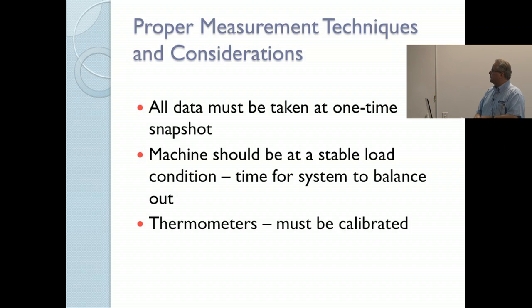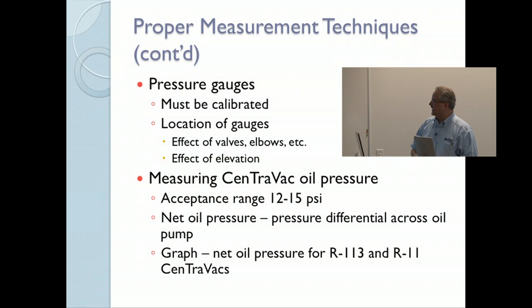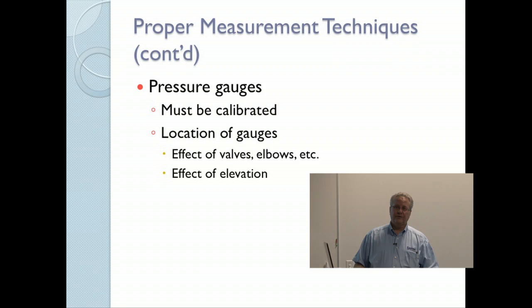Some proper measurement techniques and considerations. Again, all data needs to be taken at one time. It's like a one-time snapshot. You don't want to take half the data and then come back an hour later and take the rest. You need to take it all at one time so you can see a snapshot of where you're at. Also, the machine should be at a stable load condition. You want the time for the system to balance. You don't want it while it's hunting. Particularly if you're first turning the chiller on, you want to give it 20 to 30 minutes for the system to stabilize before you do a log. Your thermometers must be calibrated, as well as your pressure gauges. And you want to be aware of the location of gauges and how valves and elbows nearby can affect the readings, or, if you're in a high altitude situation, the effect of altitude on the gauge readings.